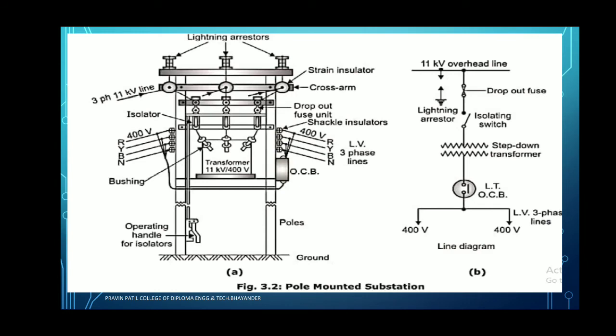Next, pole mounted substation. Pole mounted substation means the transformer is mounted on the pole. Here two poles are used, and in between them the transformer is connected. So first we have to see the single line diagram. The single line diagram shows the 11 kV overhead line.